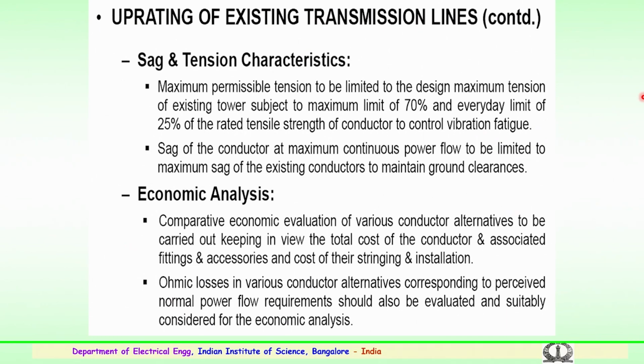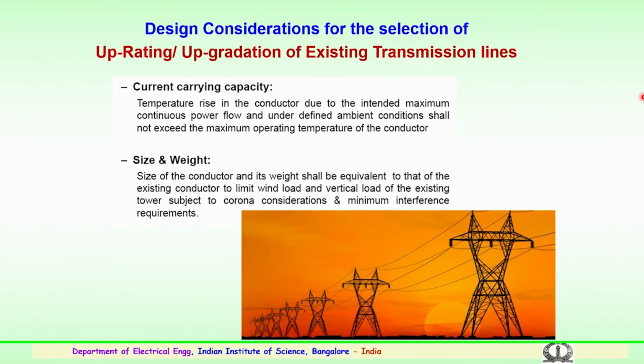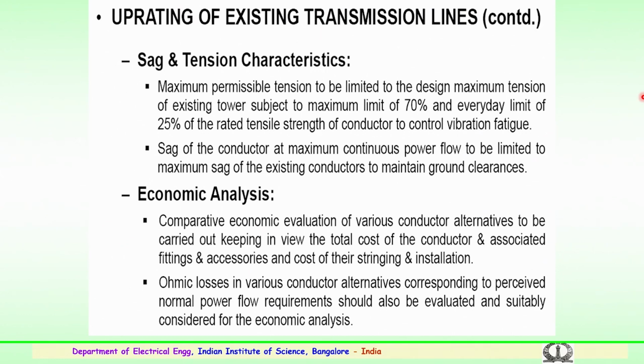When considering this, earlier we have seen some of the considerations like the current carrying capability and the size and weight. Now, sag and tension characteristics also have to be considered. So, here the maximum permissible tension is limited, by design, to the maximum tension of the existing tower, subject to a maximum limit of 70%, and an everyday limit of 25% of the rated tensile strength of the conductor, to control vibration or fatigue due to vibration or wind.